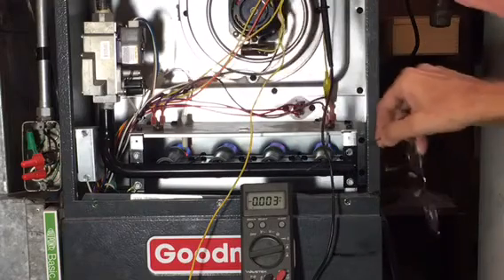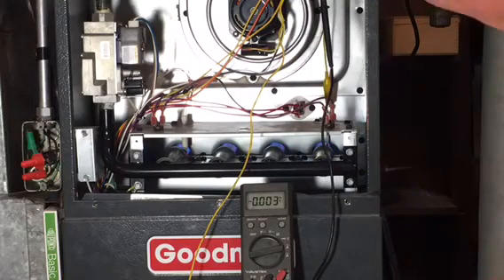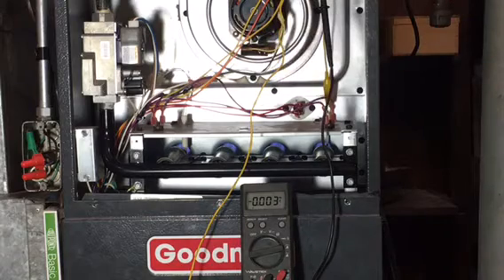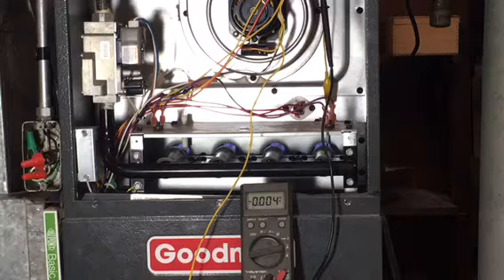Okay. Flame sensor is giving us 0.003 milliamps, which, let me check, is in the good range as I recall. We want it to be 1 to 4 microamps, or 0.003 milliamps. So that is checking out. We'll just leave that in, and it has to heat up before the main blower goes. Gets the heat exchanger nice and hot before it starts putting air around her. There she goes. She's starting to go up.